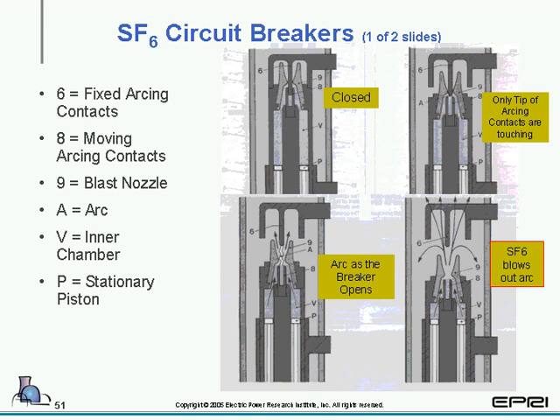In the very upper left corner, you'll see that the breaker is in the closed state. In the upper right, only the tip of the arcing contact is touching, and you'll see that point 8 is moving away. That is the moving contact structure. It's actually moving down. And point 6 is the stationary or the fixed arcing contacts. Look to the lower left.